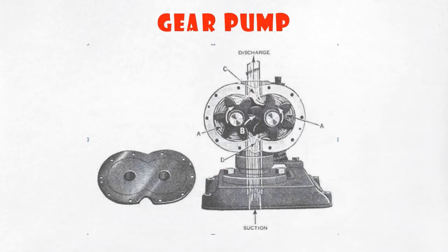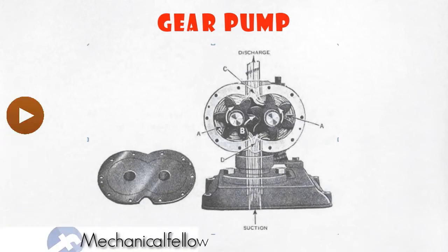This one is the gear pump. Any liquid which fills the space A between two teeth must follow with them as they revolve. In the area where the two gears mesh, B, there is little or no space for liquid, and it is forced to discharge through C in the discharge pipe. The reduction of pressure at D causes liquid flow in the suction line.